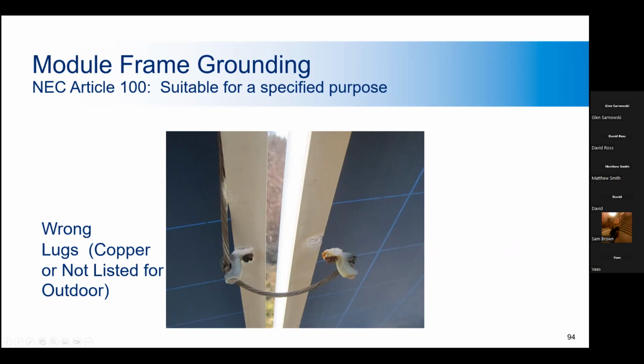Something to keep in mind is that this happened just between the build and the interconnection and the QA inspection. So the screw had already corroded to a point where it broke away from the panel frame in that short amount of time. So if the equipment's not rated for use in the environment where it's installed, it can fail very, very quickly.